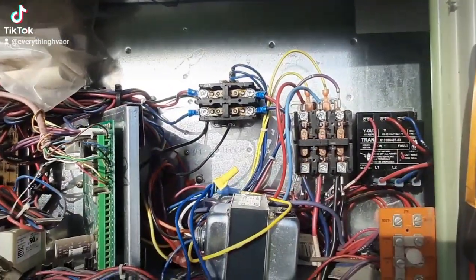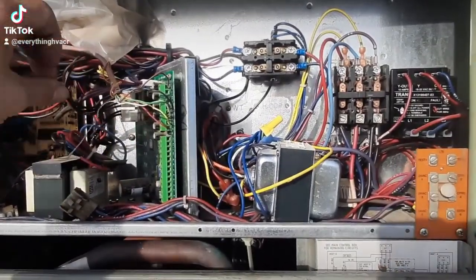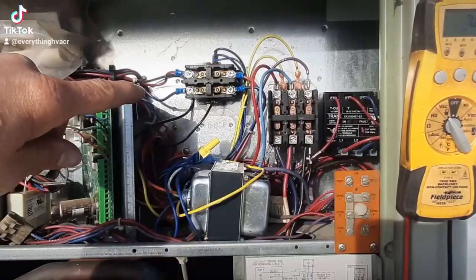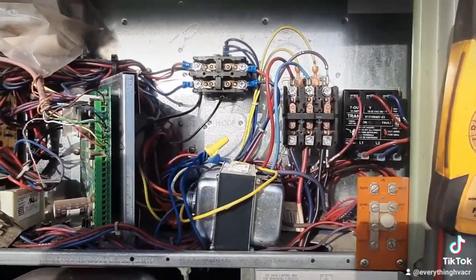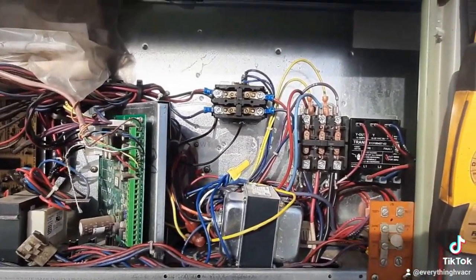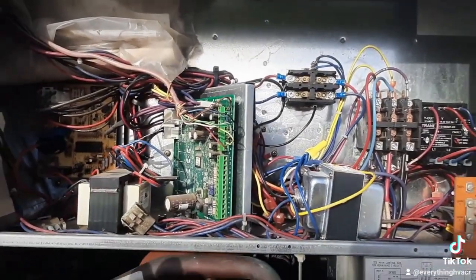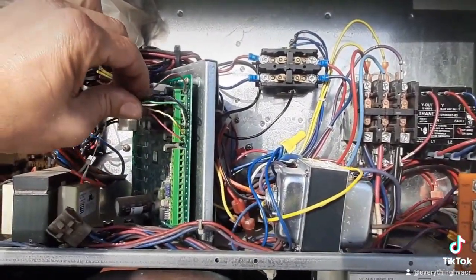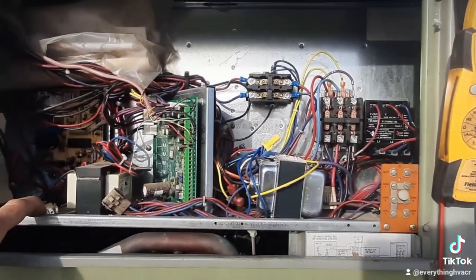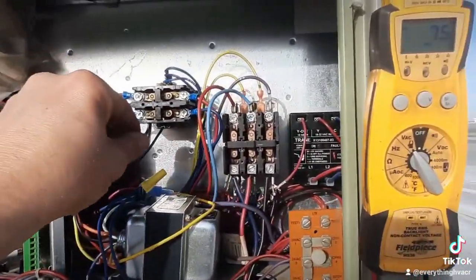That's because of the triac — I believe it's a triac they're using in these boards. I'm getting the back-feed of voltage with that wire disconnected, and it sure looks like when you pull that wire off and check it, that contactor should be energized. Just a weird little deal. Know what you've got when you're dealing with this stuff, because a lot of guys get tripped up on Trane units.